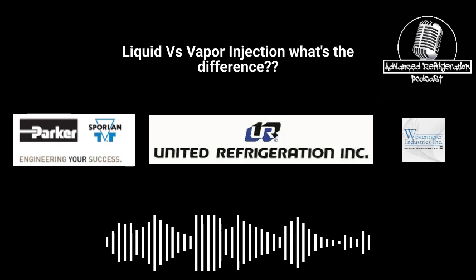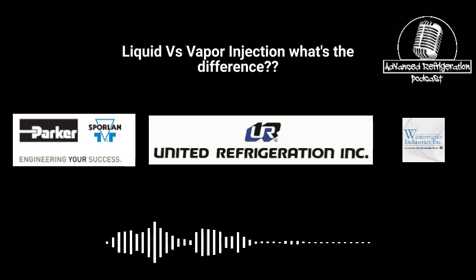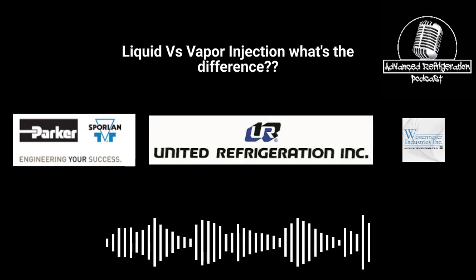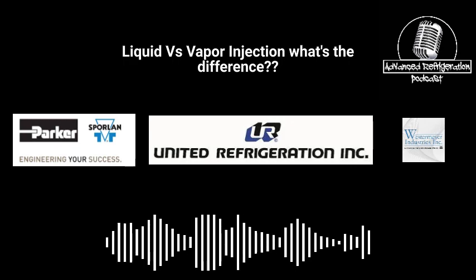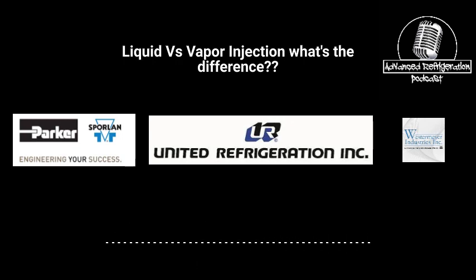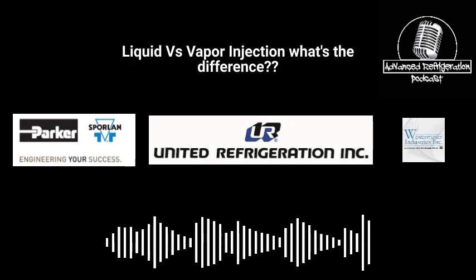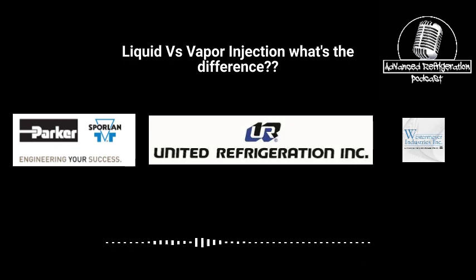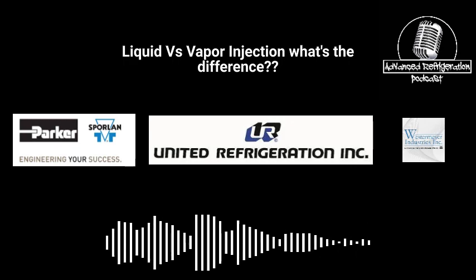But no, you want to be careful with that. But like I said, with that vapor injection with the subcooler, you get that canceling out, and then you make that compressor more efficient because now you're feeding that compressor. Say your subcooler is set up for 50-degree liquid and you're running a 40-degree evaporator, okay, and you've got 10 degrees of superheat. You're running a 50-degree interstage temperature into those compressors, and that's going to cool it off a lot more than what you have coming down your suction. That's why it's essential for it to be set up and working.